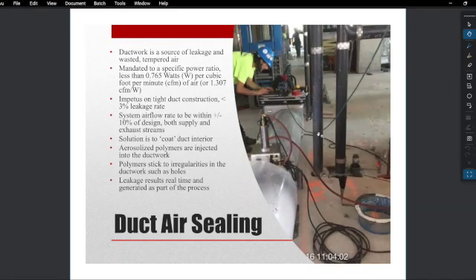We have to make sure that our ducts are really tight for installation. We have to meet certain CFMs, and the unit has to operate within a certain efficiency. For example, on my project at 425 Grand Concourse, we have to meet a 0.765 watts per CFM power consumption from the unit, which means that what the unit is designed to deliver has to be delivered, and that means we need tight ductwork so we're not spilling air where it's not supposed to go. So there's an impetus on a less than 3% duct leakage rate, and a system airflow rate within 10% of the design, for both the supply and the exhaust streams.